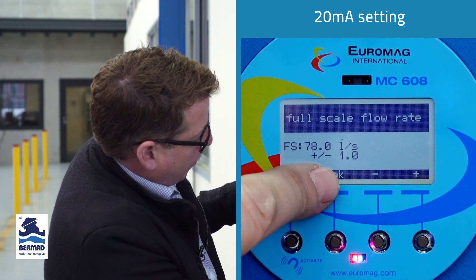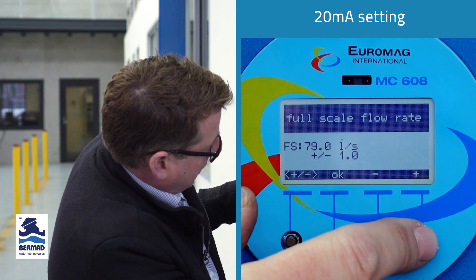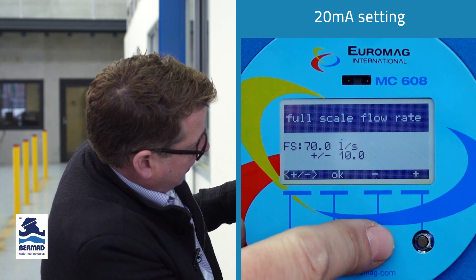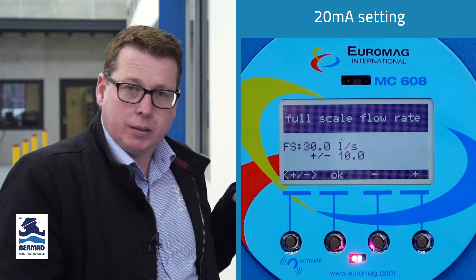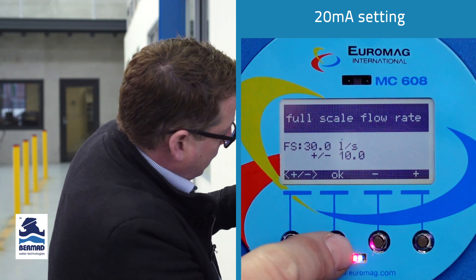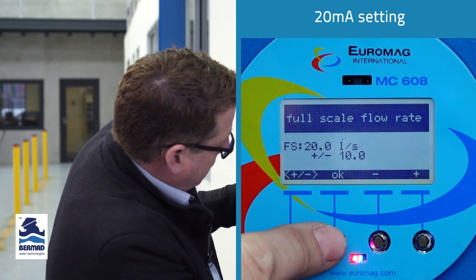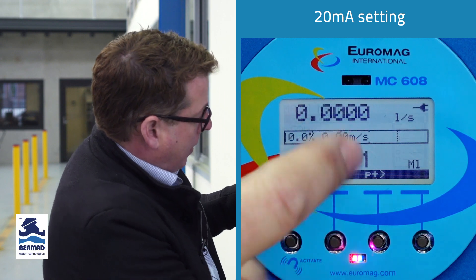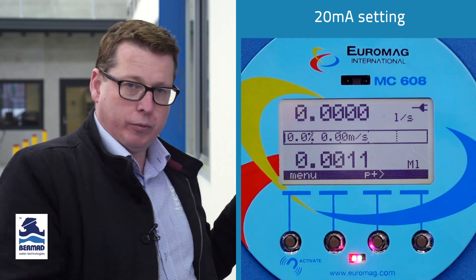Pressing once more gives 1.0. We might increase that to 80, then set the increment to 10 so we can change it by lots of 10, and bring it down to 30 liters a second — that's what we expect as our maximum flow rate for a 4-inch line. Press OK, and it's that simple. Now we've set up our 4 to 20 milliamps to be 0 to 30 liters a second.